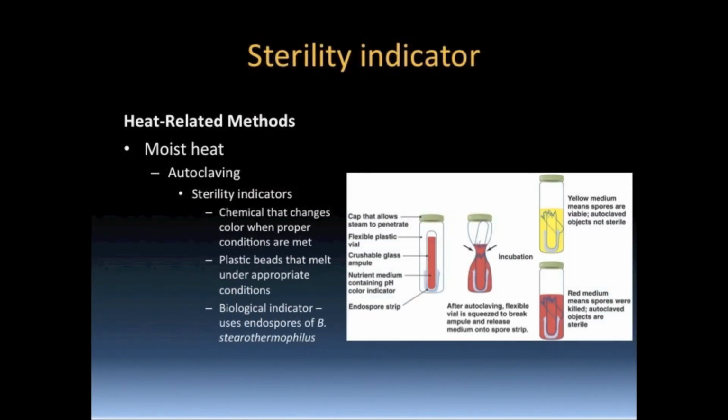To ensure that sterilization is accomplished, an indicator is utilized. In some cases, a tape that is impregnated with a color indicator may be used. A piece of the tape is placed on an item to be sterilized. After autoclaving, the color indicator will appear if the appropriate pressure and temperature was achieved.